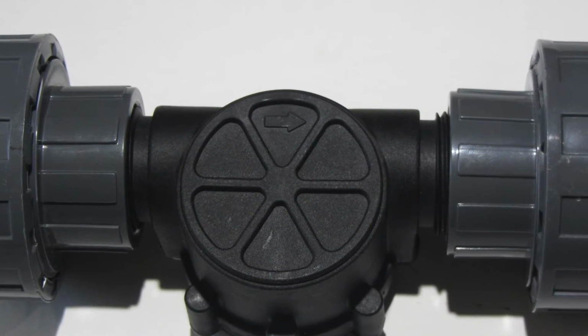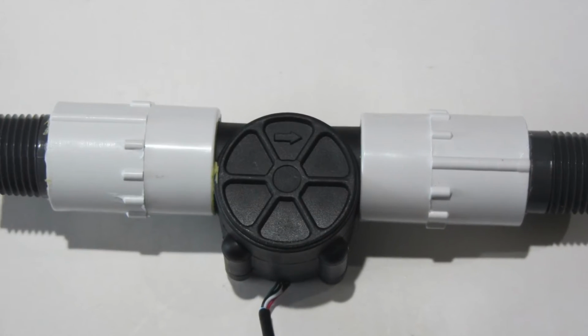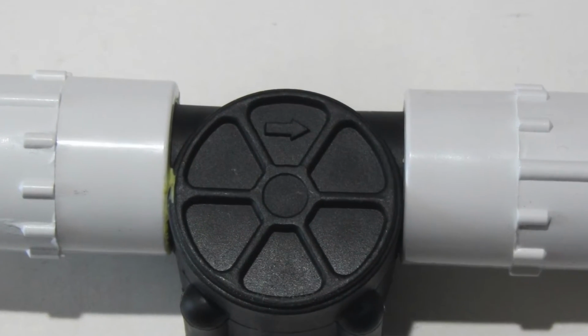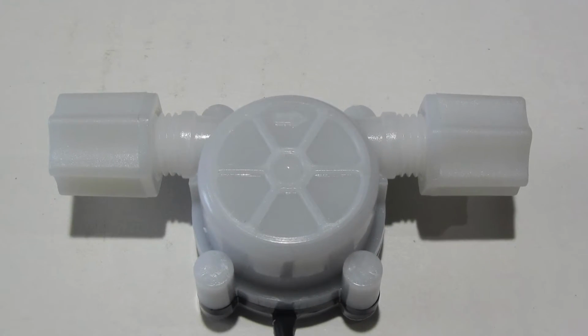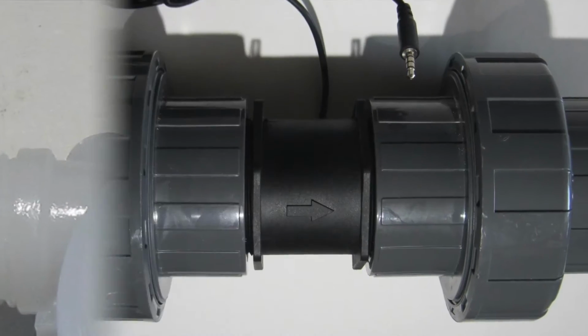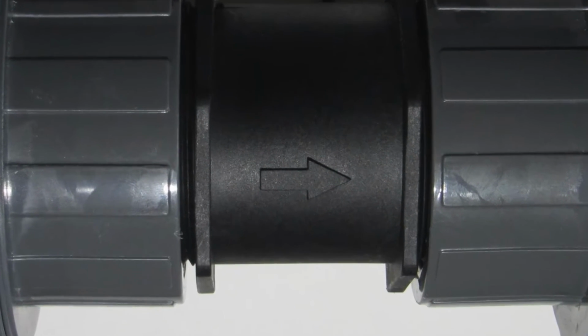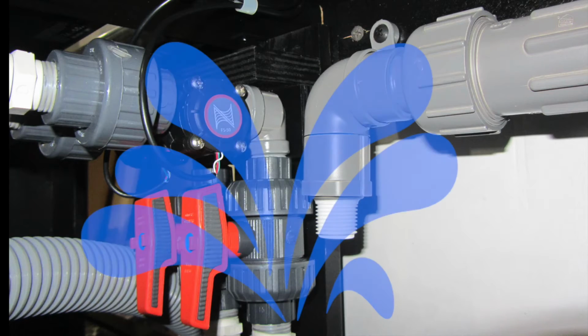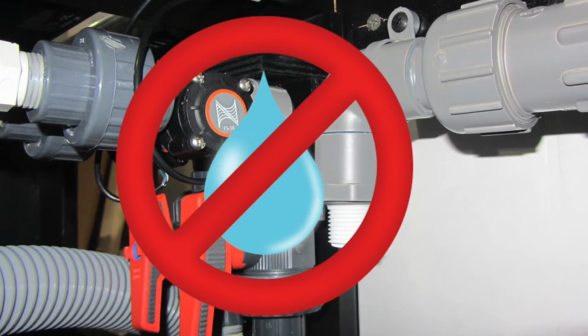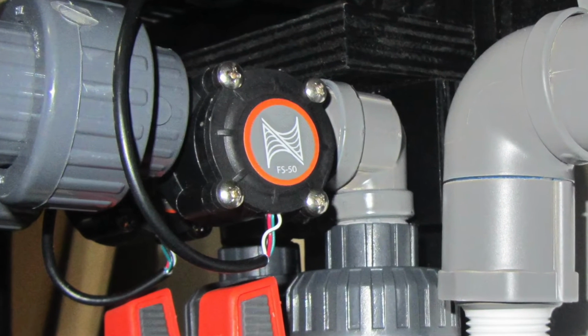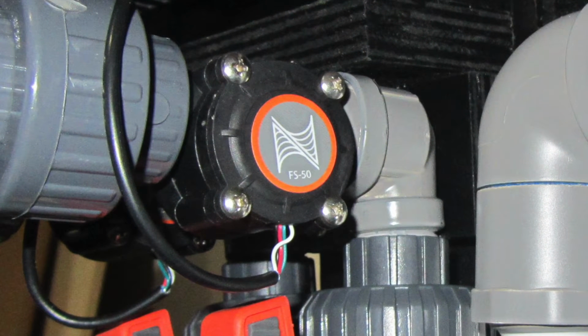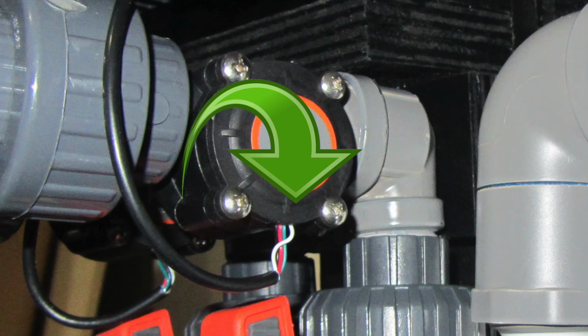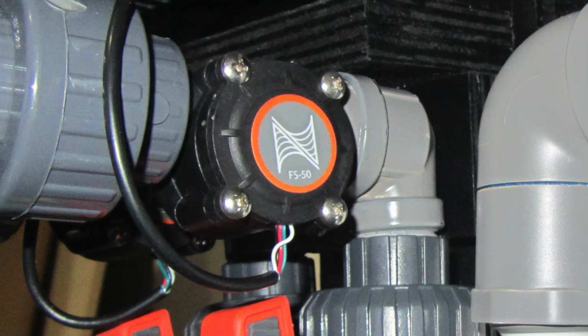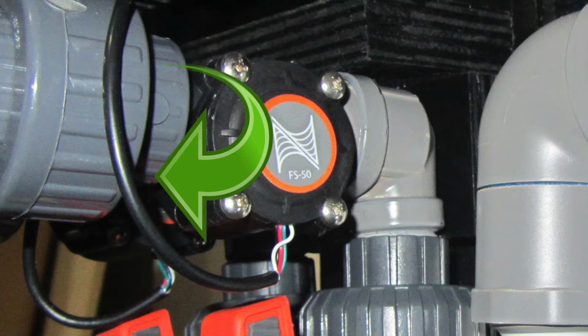When installing the sensors, it is important to notice the direction of flow indicated on the housing of the flow sensors shown in these pictures. If the sensors are not installed correctly, this could affect the reading that the flow sensor sends to the FMM. Flow sensors are water resistant and will withstand an occasional splash or drip, but they are not waterproof. For the best resistance to such splashes and drips, when installing, orient them so that the point where the cable enters into the body of the flow sensor is pointing down, and if possible, also give the cable some slack so that you are not putting any strain onto that cable.